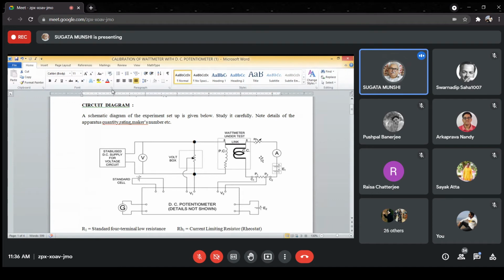Often students give a long answer that phantom loading will reduce the power loss in the current coil, etc. That will not happen. At the same supply voltage of 100 volts for this wattmeter, whether you use a physical load or a phantom load, the current through the current coil has to be 1 ampere so that the reading is 100 watts. The current through the current coil should be 0.5 amperes so that the wattmeter reads 50 watts, like that. So the current through the current coil will be the same in both cases if the supply voltage is at the rated value. In our case, it's 100 volts. In some cases, it can be as high as 600 volts. Anyway, this is why you use phantom loading. Is that clear?